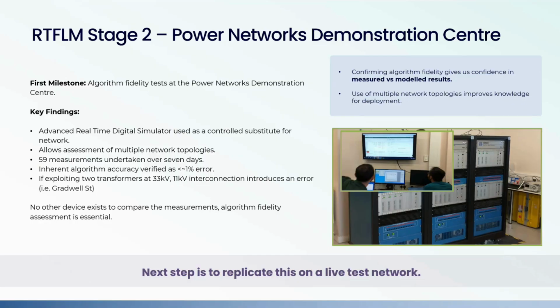Here's a picture of the real-time digital simulator and us looking at screens, looking for test results. We did some 59 tests at the PNDC. We tested both 11 and 33 kV bus voltages under different conditions. We changed the input frequency. We confirmed the effect of interconnections.